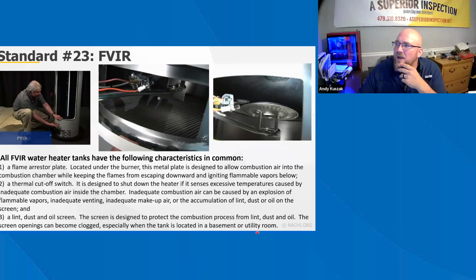All right. FVIR stands for Flammable Vapor Ignition Resistance. In 2003, a new standard for water heaters was developed and phased in. It states the water heater should not ignite flammable vapors outside the water heater created by spillage of gasoline onto the floor. The Consumer Product Safety Commission found that thousands of fires, injuries, and deaths are related to water heaters. Most of these incidents were caused by improper storage or handling of spillage of gasoline.